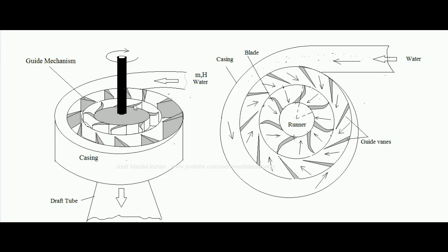Water from the casing enters this guide mechanism in the radial direction at a particular angle and is directed to interact with the rotor, or runner. The runner also consists of blades. When water hits these blades, it gives a push, and a torque is developed over the runner because force into the radial distance is torque.